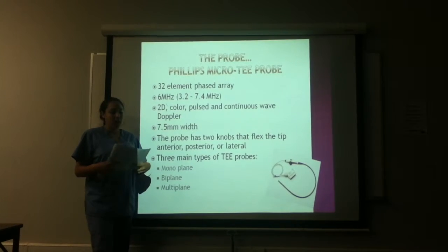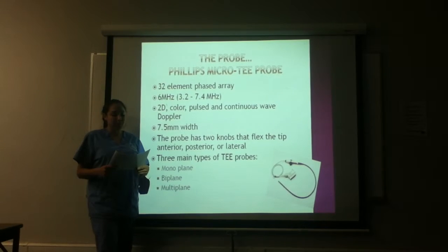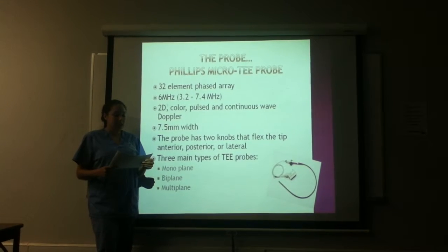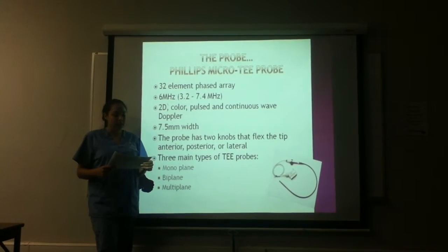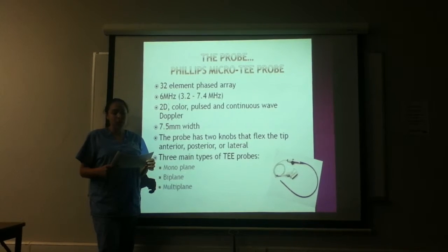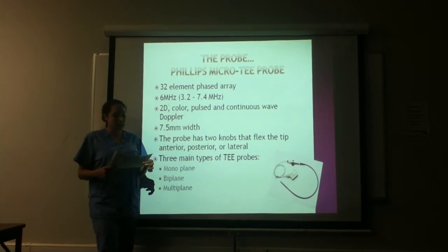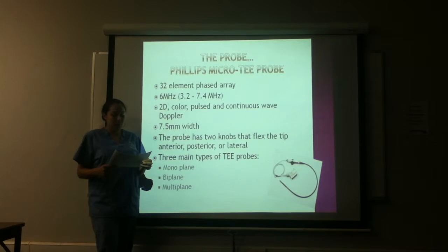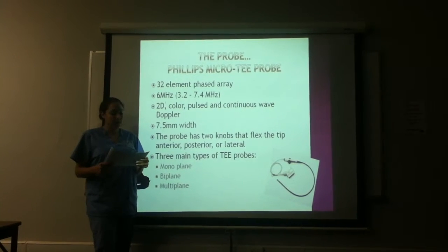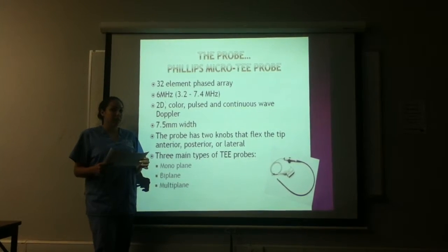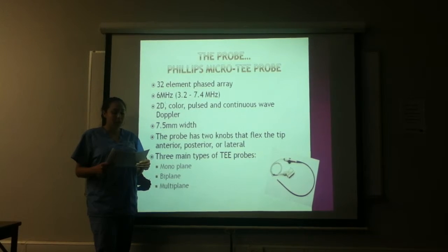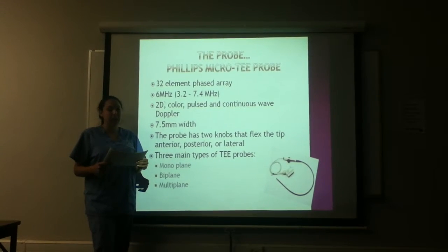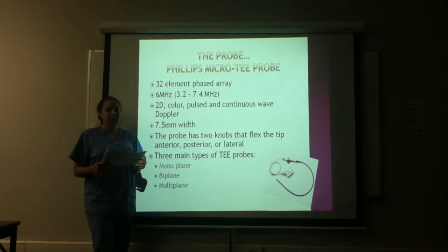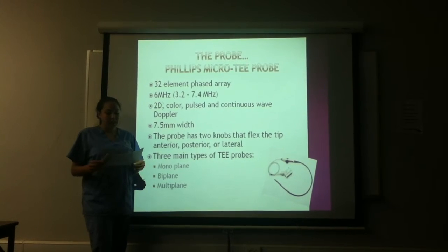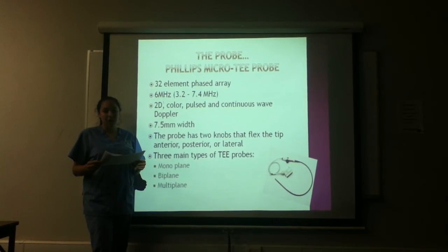The probe. A Philips Micro TEE probe. It has a 32-element phased array, 6 megahertz, 3.2 to 7.4 megahertz. A 2D color, pulse, and continuous wave Doppler, 7.5 millimeters in width. The probe has 2 knobs that flex the tips anterior, posterior, and lateral.